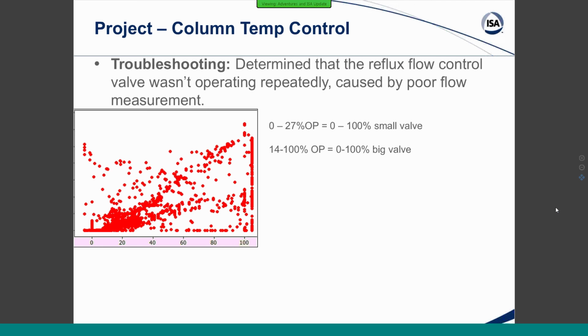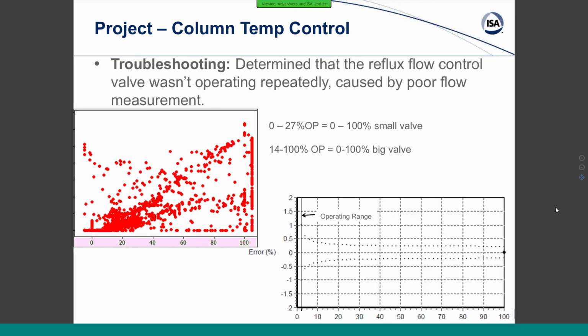This isn't actually a control valve issue though in this case. This is a flow element issue. The flow meter that we had installed on this particular unit was sized for a completely different product that had a much, much higher reflux flow. So we are actually trying to operate this flow meter in the range to the left of that little operating range line. Our error is completely exponential at this point, and that's what's giving us the very, very poor control.